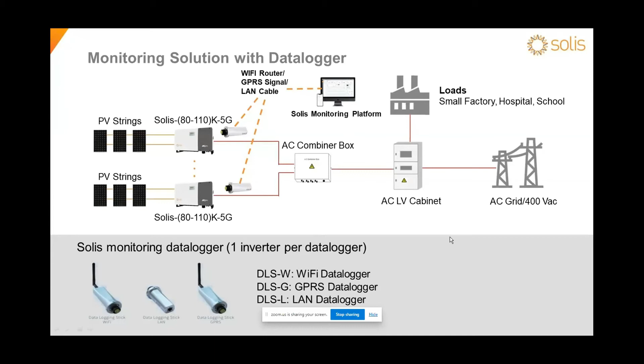In addition to the stick, we also provide a monitoring box, the so-called DLB. It's a Datalogger box. It's different from the Datalogger stick: the Datalogger box can connect up to 10 inverters for one box. And the box will also go through Wi-Fi or GPRS to the monitoring platform. This part is pretty much the same as the DLS. Between the inverter and the monitoring box, it is connected by RS485.